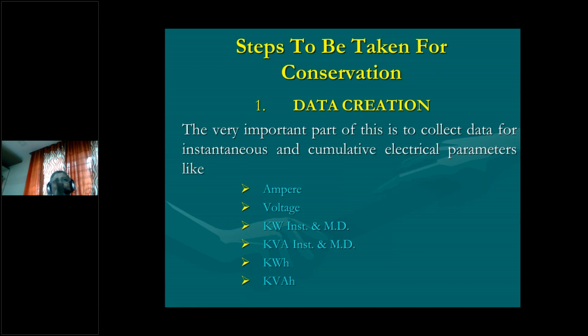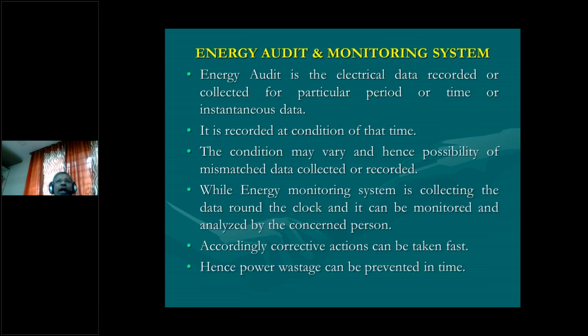Now I will move to next slide. Now here we will start about the energy audit and monitoring system. Energy audit is electrical data recorded or collected for that particular period of time, or instantaneous data. There may be two parameters in the energy audit. One is the instant, that is your demand was so and so, that time demand was there. And cumulative parameter, that particular reading.